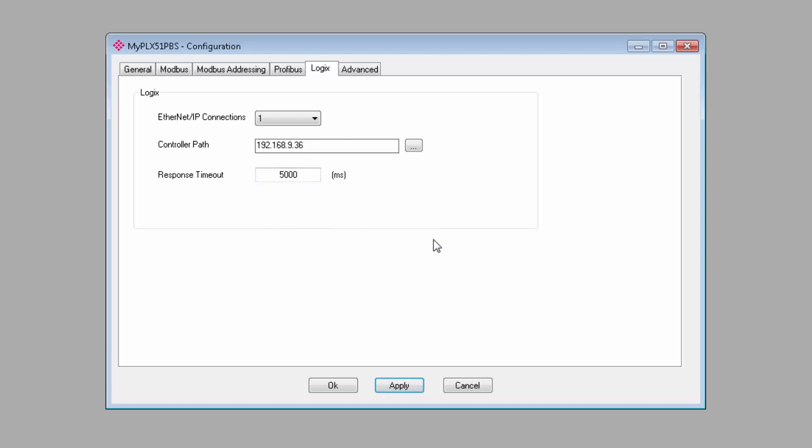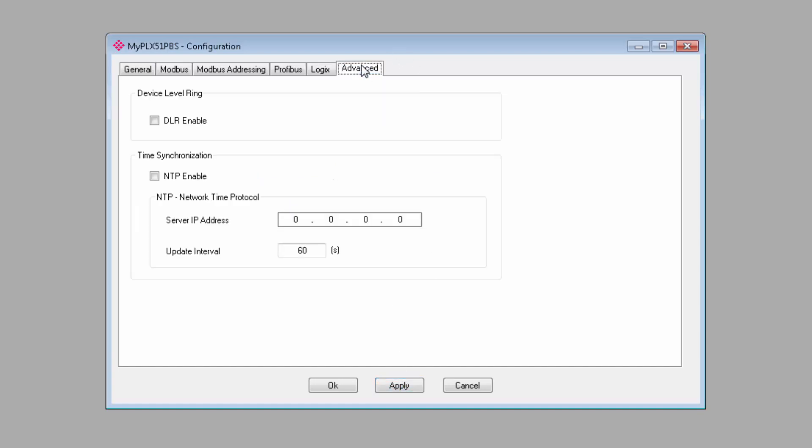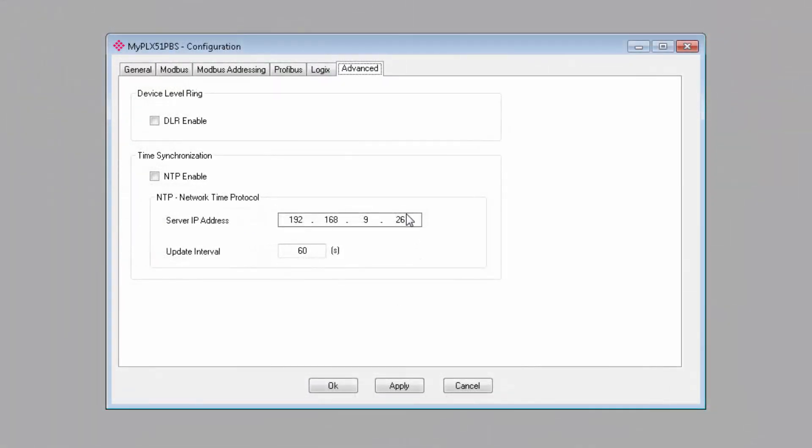Under the Advanced tab, we can enable Device Level Ring and set our connection to an NTP server. If you plan on connecting two devices on a DLR, you should enable DLR here in order to make use of the redundancy features. And, for your information, if you don't use DLR, then the two ports on the module can act as a two-port switch. As for the NTP feature, if you do need to use it for your application, you would enter in the IP address of your NTP server here.